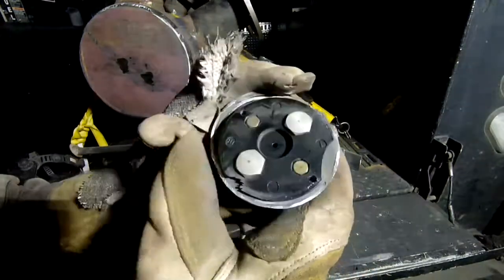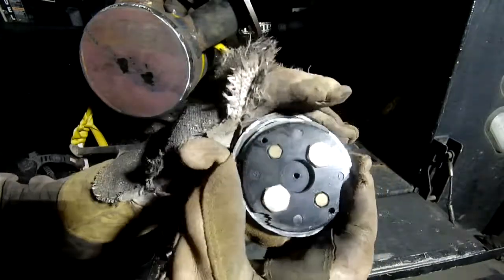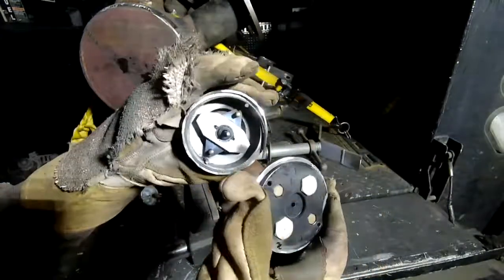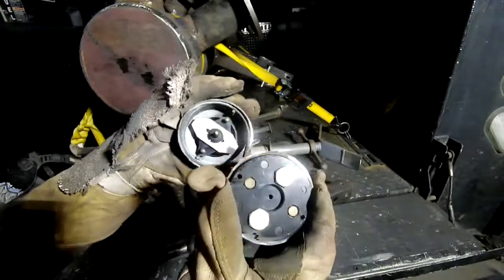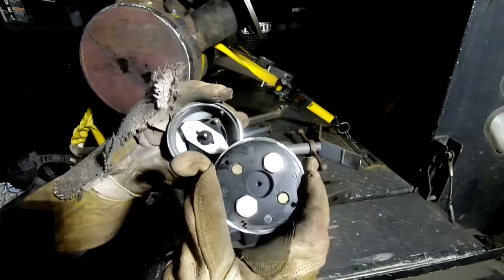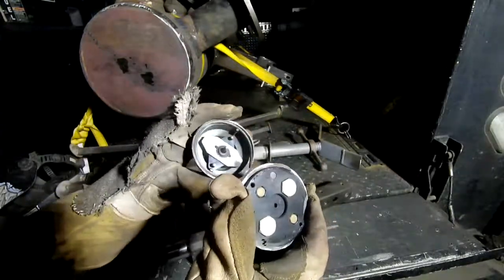Look at that little tiny area that's making the connection. I can't recommend this brand of switch because both of these switches were giving me all kinds of problems when you tried to run amperage through them. Maybe you get what you pay for in an 800 amp switch.